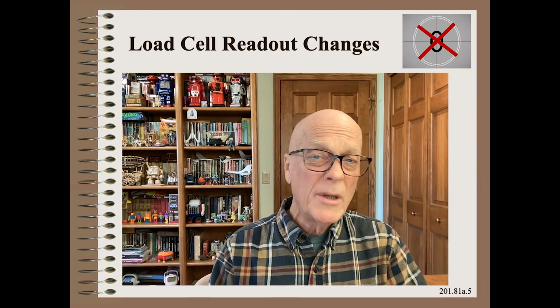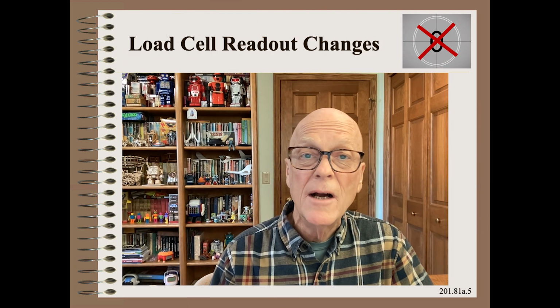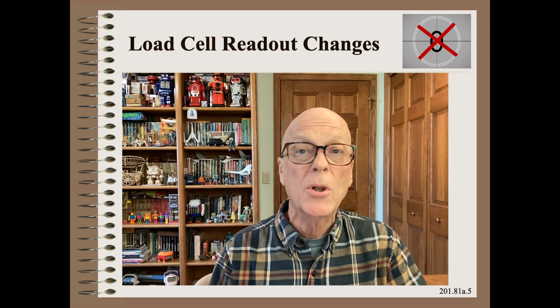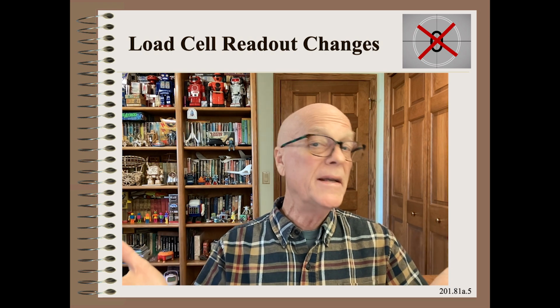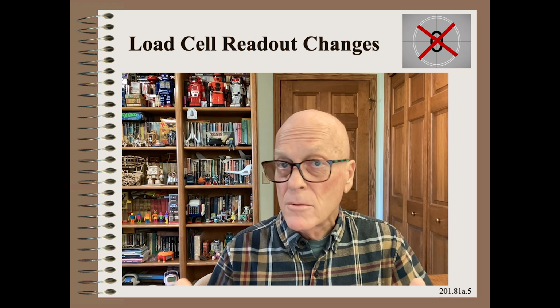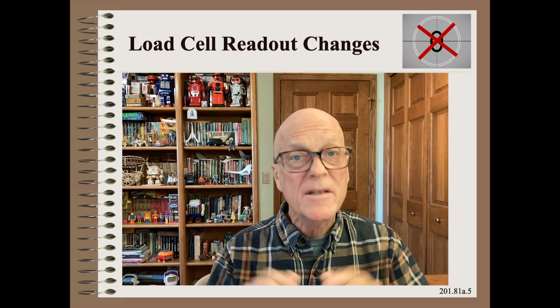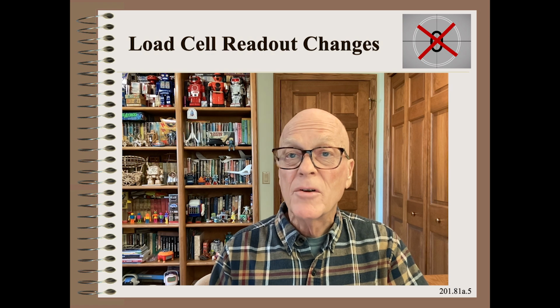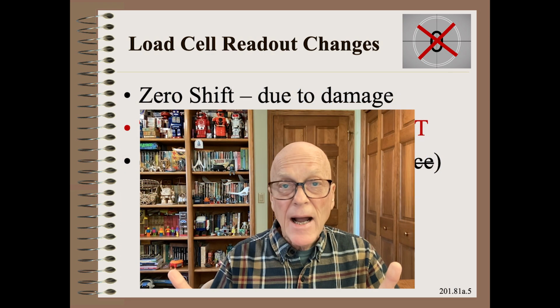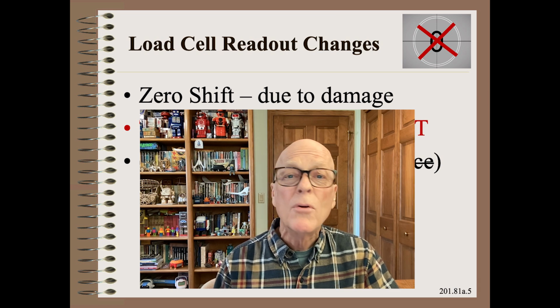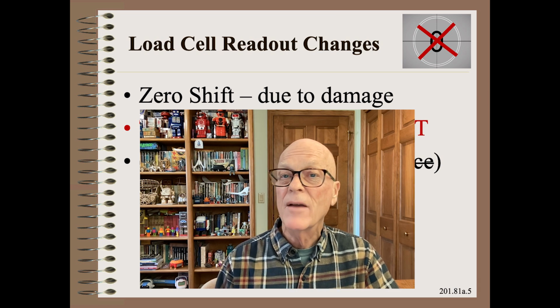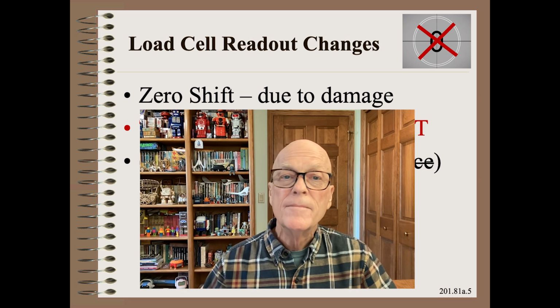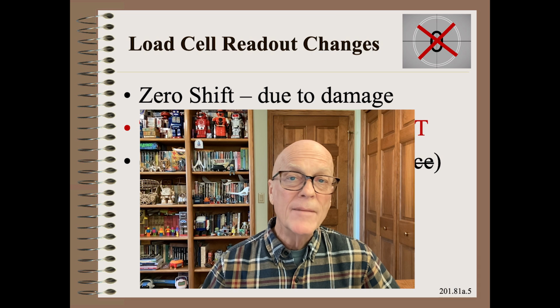Every operator should be taught to check the zero of the load cell once a shift or when feasible or possible. This is quite easy. When the web is off or loose, the tension should be zero. And so too should be the load cell reading. If not, maintenance should be called. This is analogous to checking fuel level in your car before driving away, or in much older days, checking the oil also.